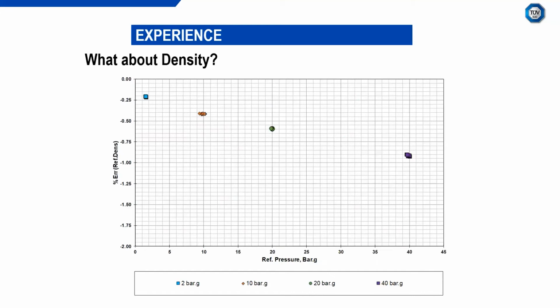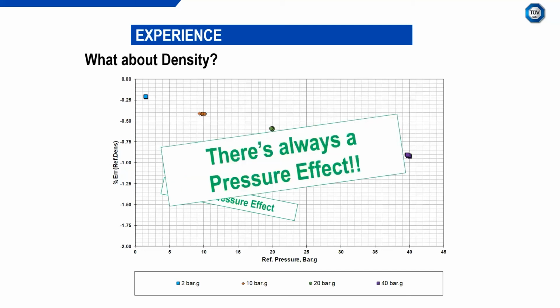Now, what about density? One of the main benefits of Coriolis meters is that you get mass flow, you can also get volume flow by combining with the density, but you also get density from the frequency output of the device. Density also appears to be affected by pressure, so this device in particular was significantly affected. Other models and manufacturers have seen, although they are affected by pressure for the density output, it's not quite as significant. For this presentation, I've used an example where the density pressure effect was fairly significant. But again, it's linear. And linear is always good news because it is correctable. So there does appear to be a pressure effect for the density.